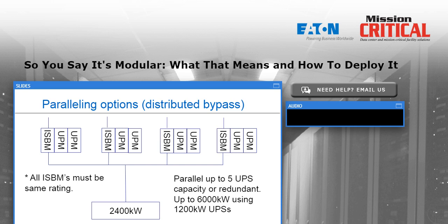And in general, for battery systems that are in the range of 2 to 3 years old, it's reasonable to go ahead and parallel new batteries with old batteries. There is a tendency for the older batteries to pull the new ones down to their level, but it is something that can be considered. If those batteries that I originally installed are, let's say, 4 years old, then do I want to bring in new batteries and put them in parallel with the old ones? That's the line where, in general, most vendors are going to recommend, nope, let's go ahead with a whole new battery system there. It becomes a little bit risky to parallel very old batteries with brand new batteries. And by risk, I mean the possibility of shortened life for those new expensive batteries that you just bought.